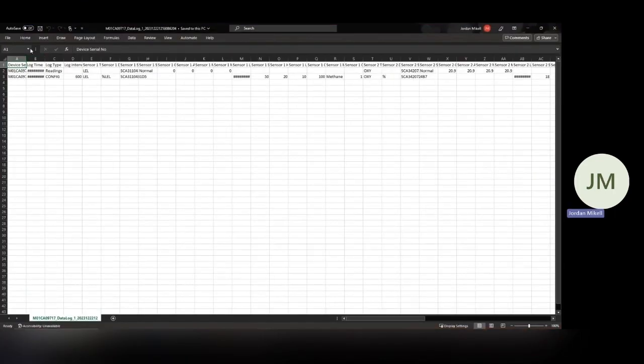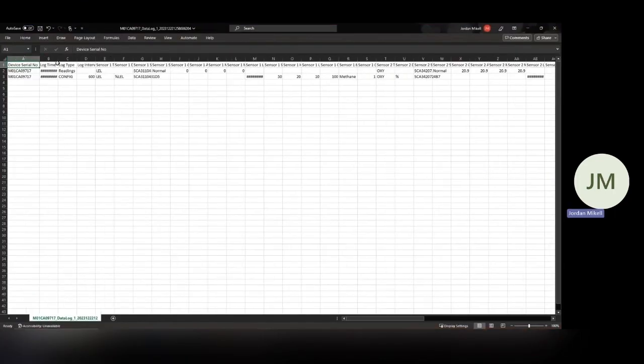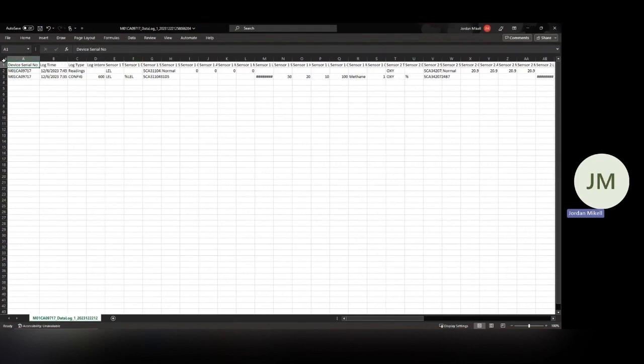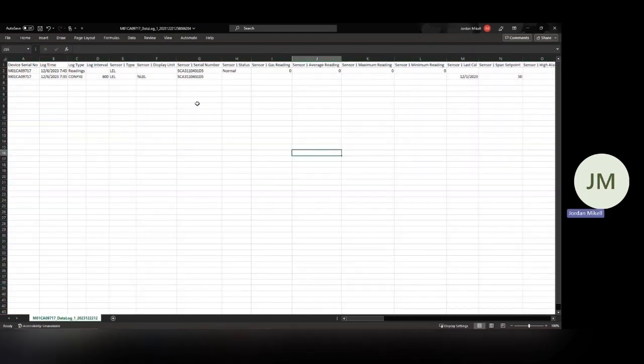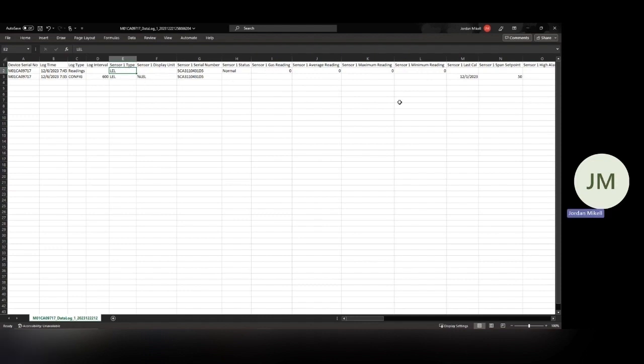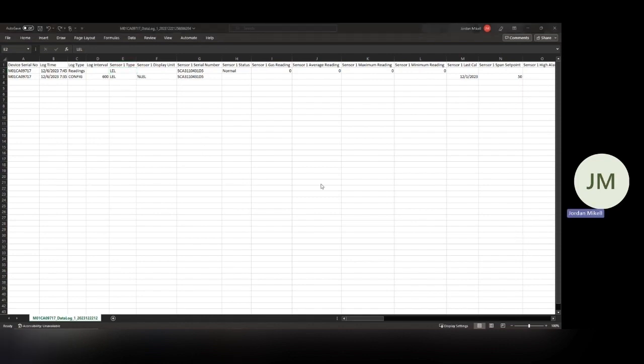So here is my data log. This one only logged one piece of data, but you're going to find everything here. And you'll see now that with this software, instead of just indicating the sensor and then all the readings underneath it, you're going to see a sensor one type indicating what sensor that is for the multi-ray. For a Toxi-RAE, you're only going to see one sensor, but MultiRAEs and QRAEs, those are multi-gas monitors. So you will see multiple sensors and it'll tell you what the sensor one type is and then your readings.